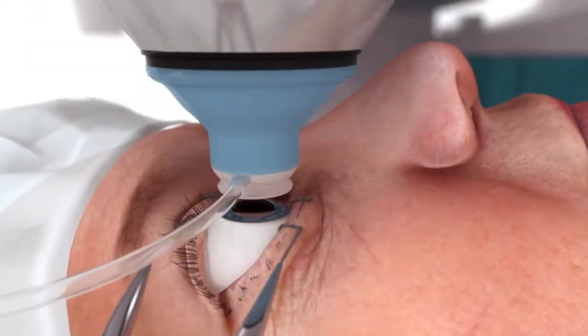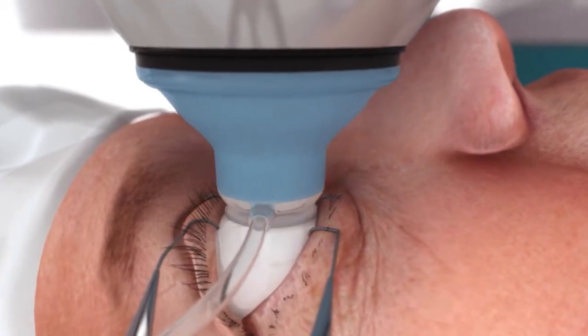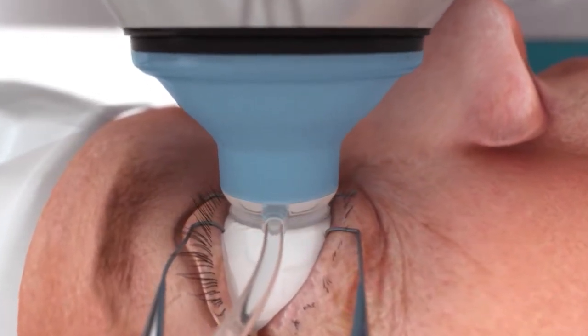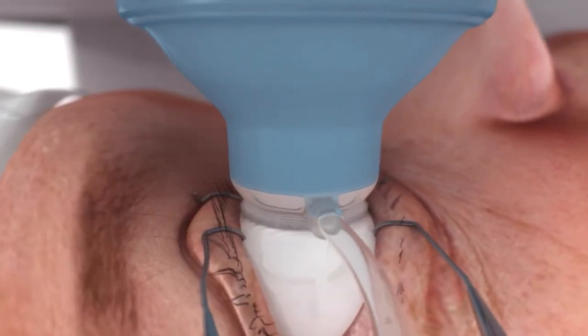Using the autofocusing video microscope, the surgeon guides the patient interface to the corneal surface. The LenSx laser was specifically designed for this small, universal interface, which has been validated in thousands of procedures.